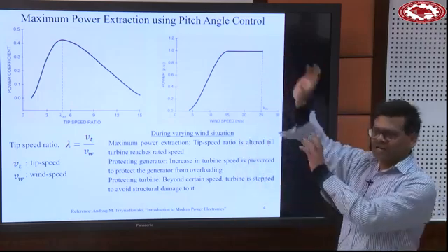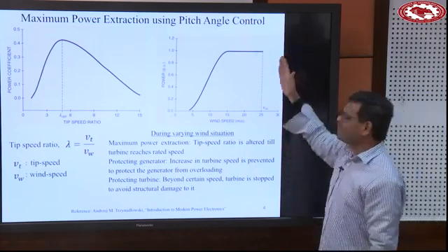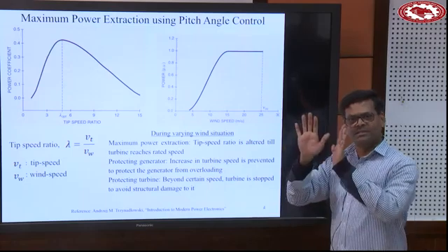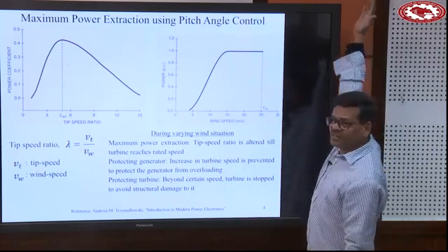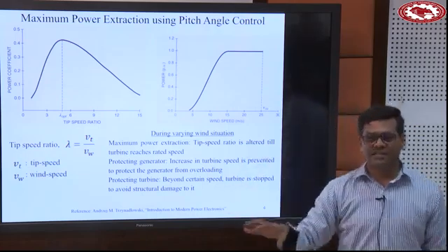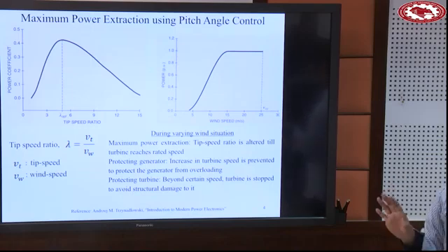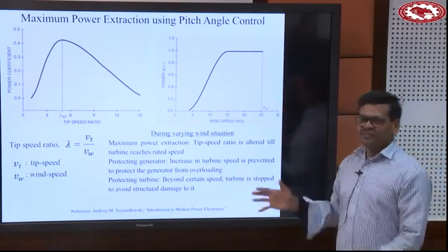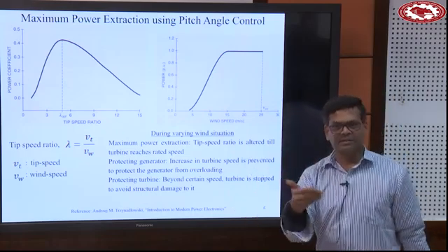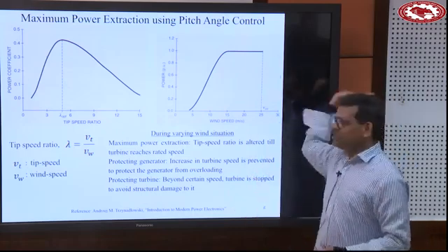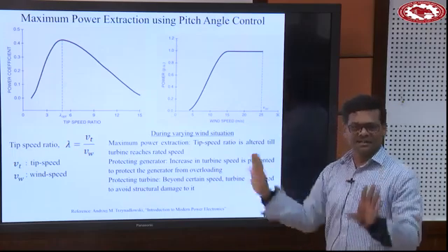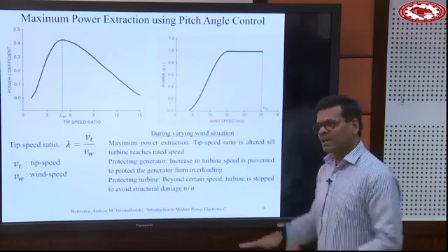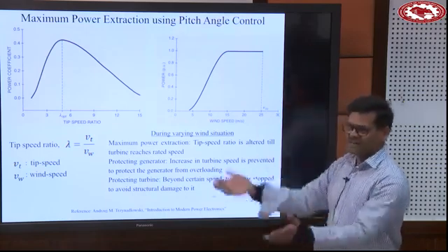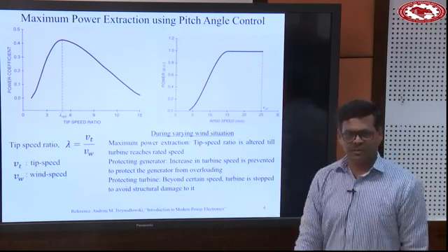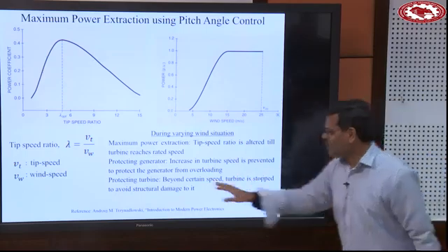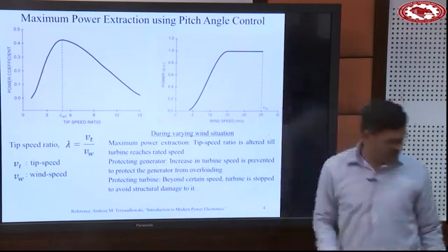In many places the blades are broken and thrown out actually. So then the whole system is stalled. The whole system is stopped. Although we get huge electrical power, considering the mechanical integrity of the system, the complete plant is shut down. Is that clear? From 15 to 25, we want to take care of the generator, otherwise the current in the windings of the machine will be huge. But beyond 25, we are completely shutting down, otherwise the blades and all will be broken. So to take care of the entire system, even if it comes for just a few minutes, it has to be stopped completely. Something written: protecting the generator here, protecting the turbine beyond 25 meter per second.